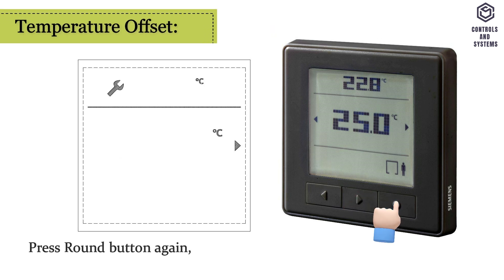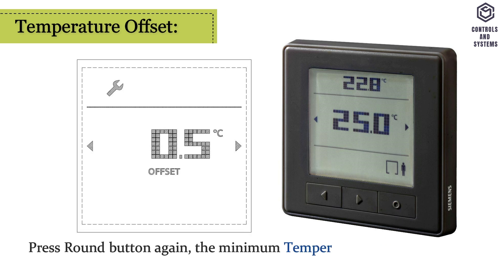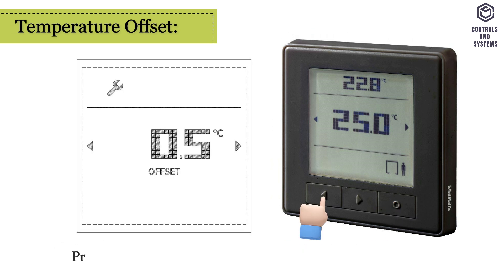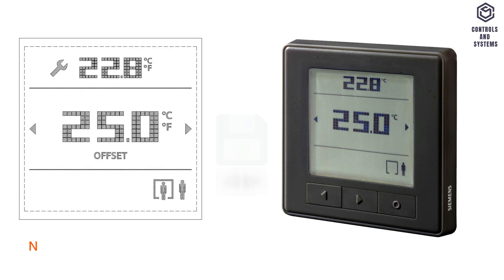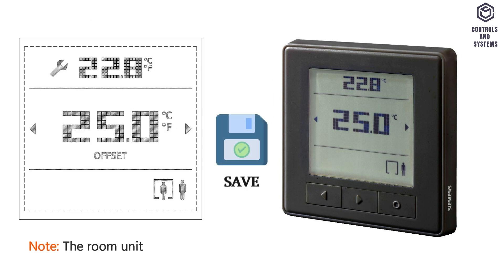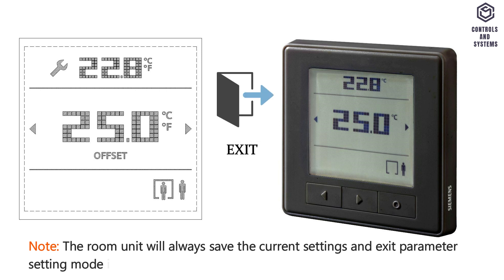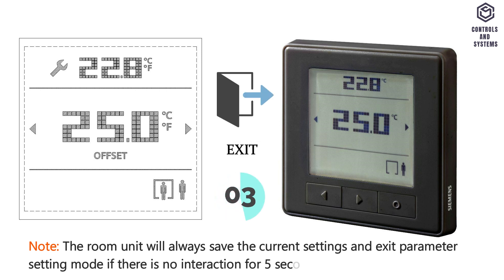Temperature offset: press the round button again, the minimum temperature offset value appears; press left button or right button to adjust the offset value. Note: the room unit will always save the current settings and exit parameter setting mode if there is no interaction for 5 seconds.